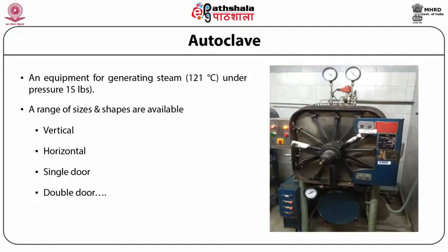So they will just require maybe a liter of media to be done in a day. And therefore they have small autoclaves in which you sterilize the media. And why it is important is that at a pressure of 15 pounds and temperature of 121 degrees centigrade, 15 to 25 minutes, depending on how much media is in each vial, is adequate to sterilize it.